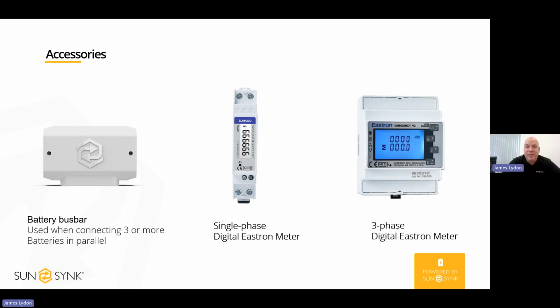Eastron meters. All our inverters come with the hardwired CTs as standard in the box. If you don't need a wireless CT, but the run from the inverter to the incoming supply is more than, let's say, 15 meters, you would typically use an Eastron meter. We stock these: a single phase Eastron meter and a 3-phase Eastron meter. These are connected back to the inverter on a full patch lead, which avoids any comms or interference issues. If someone tries to extend the included CT to, let's say, 30 meters and they've got it trunked with all the DC or AC cabling, we're going to get a lot of noise on that line. So in those instances, we always say to use the Eastron meter.